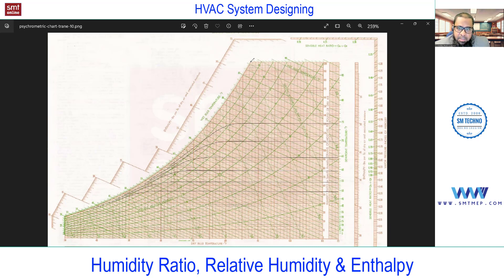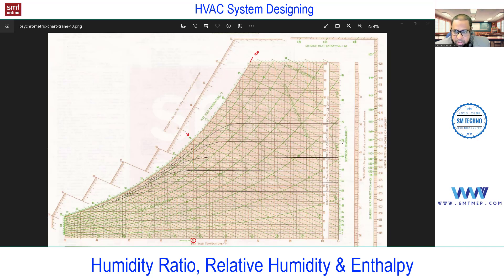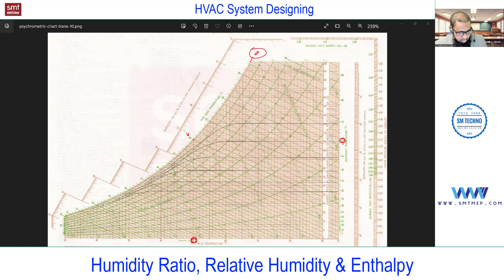On the psychrometric chart, the curved line is the 100% RH saturation curve. The dry-bulb temperature is along the bottom, and the dew-point temperature is read on the right. If I plot a point on the saturation curve, for example at 70°F, the dry-bulb, wet-bulb, and dew-point temperatures all read 70°F — confirming that all three are equal at 100% RH.